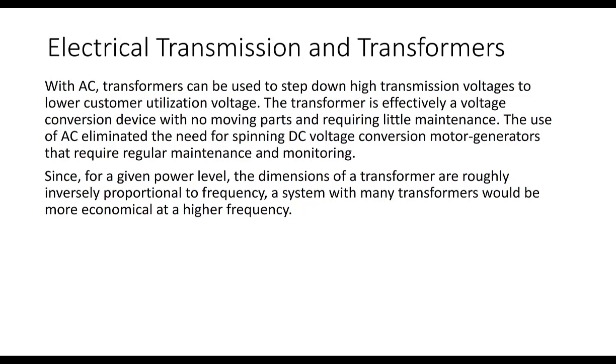All the more reason why moving towards electrification as our source of power offers a wide range of both space saving and maintenance benefits over more active motor and generator source transmission and transformers. Since for a given power level, the dimensions of a transformer are roughly inversely proportional to frequency, a system with many transformers would be more economical at a higher frequency - another reason why the 60 hertz standard was adopted.